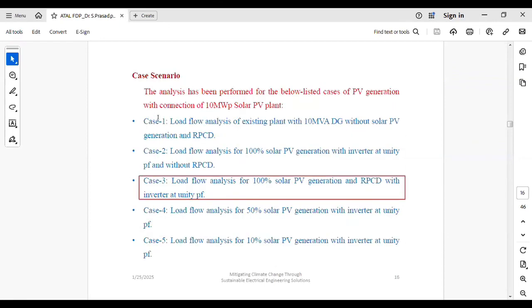So there are different case scenarios to perform the load flow analysis for a 10 megawatt solar PV plant. Case one is load flow analysis for the existing plant with a 10 MVA DG without the solar PV plant. These first two cases I have not considered. The third case I have considered to explain is load flow analysis for 100% solar PV generation and RPCD with inverter at unity power factor. RPCD means reactive power compensating device, a capacitor bank or an SVC or a STATCOM we have connected at the inverter station to maintain 0.95 lead or lag power factor at the POI. So we have to decide what the capacity of the RPCD should be.